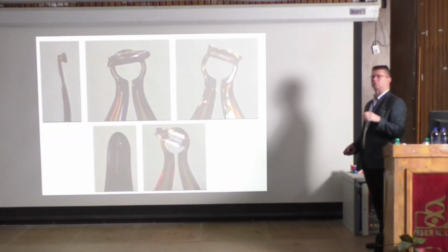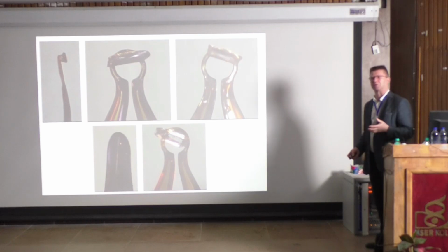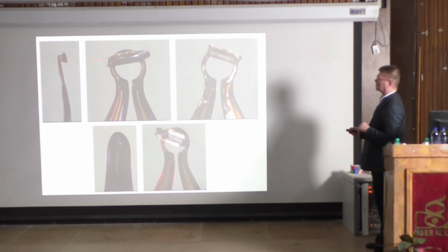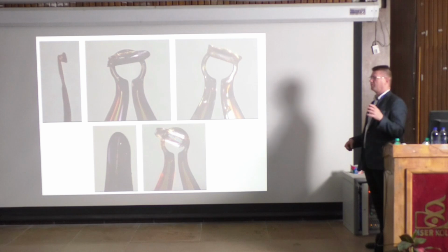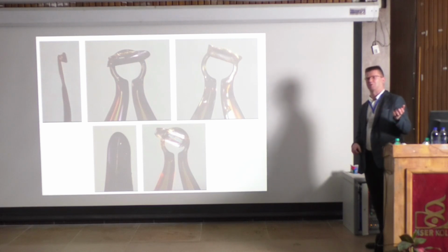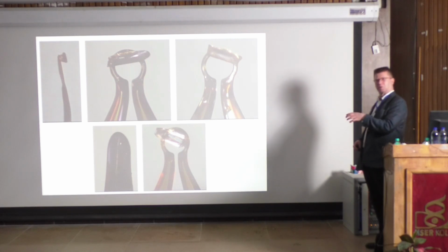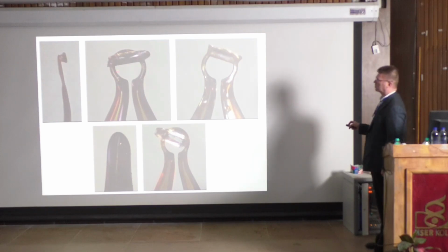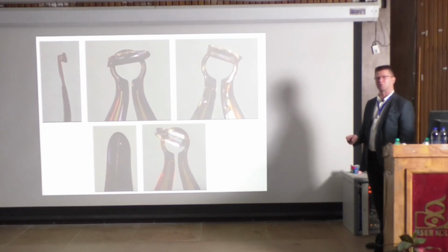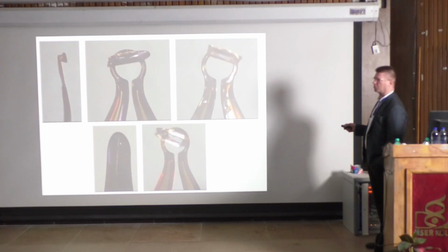How do we attach the crystal, when it's done, to the diffractometer? We need a sample holder, and this is a sample holder. If you were in my course at my university, we would go to the instrument and I would show you what it is. This is, in this case I think, 200 microns, so 0.2 millimeters, so it's really small. You do this on the microscope; the instrument has a microscope.